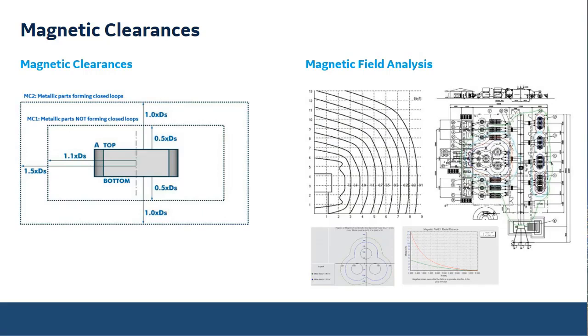If there is magnetic field flowing through a closed loop, that induces current; that current flows through the ring and creates heat, and that can be a concern, like people touching a fence and getting burned, or even worse, getting an electrical shock. This could also increase the temperature of other equipment surrounding the reactors, for example a steel post structure, or cause a bad reading on a CT that also has a core. So again, the magnetic fields and clearances will always be provided by us, and if there are still any questions about the magnetic fields, we can run very detailed magnetic field reports, like the ones shown on the right-hand side. We just need to know how you're planning to install them and your concerns.